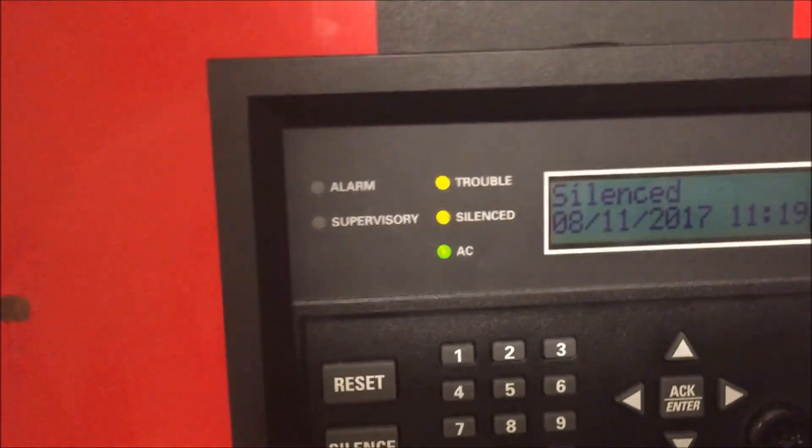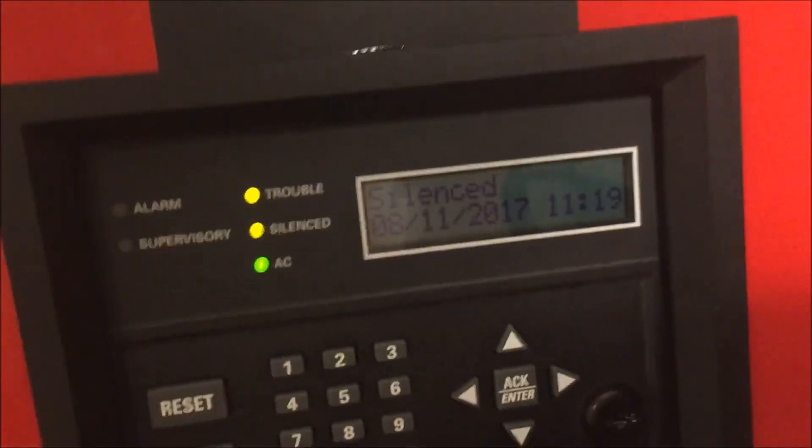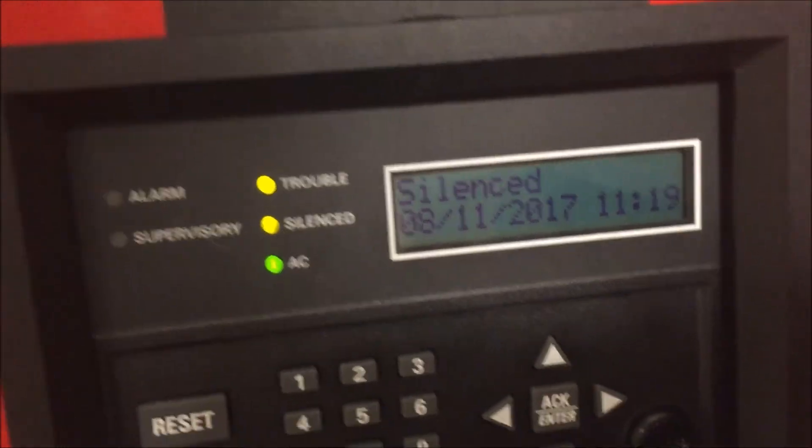When I put the Gentex NAC back in, it will complete the circuit. There we go — the Gentex is back in and you'll see the trouble go away in a second. I think smokes are the biggest thing that get tampered with, so people can actually smoke, but yeah — everything on this panel is supervised.